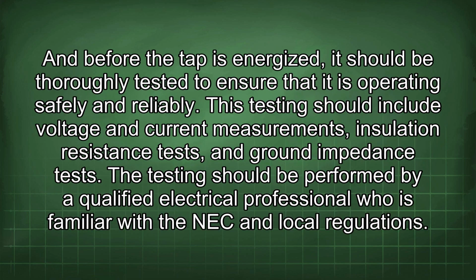And before the tap is energized, it should be thoroughly tested to ensure that it is operating safely and reliably. This testing should include voltage and current measurements, insulation resistance tests, and ground impedance tests. The testing should be performed by a qualified electrical professional who is familiar with the NEC and local regulations.